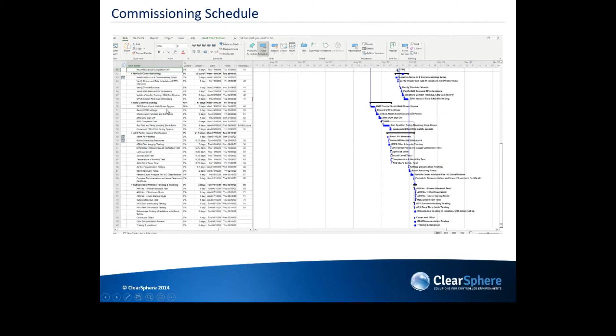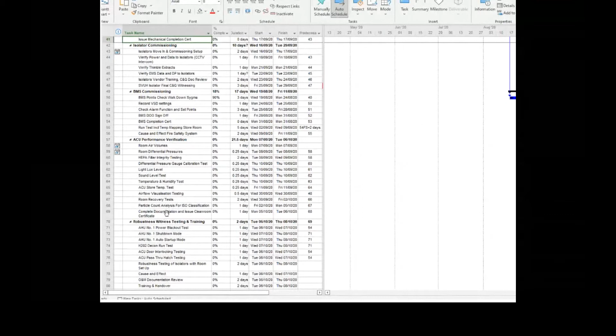And I mentioned earlier about a schedule. So this is the schedule that we set out for commissioning, which takes you down through BMS commissioning, right through to the performance verification, which are the tests I just called out earlier, and the sequence of how those tests are carried out, right through to the robustness testing that I mentioned, such as power blackout, shutting down, auto startup, etc., door interlock testing, and pass-through hatch testing. So it's pretty comprehensive, and it gives a clear picture of the sequence of how everything needs to happen as well.